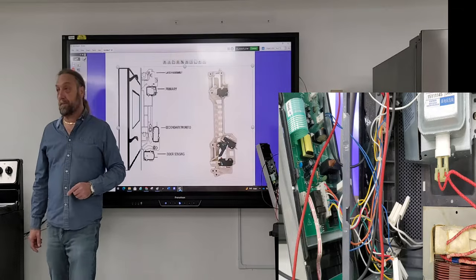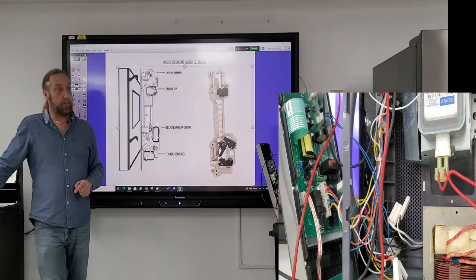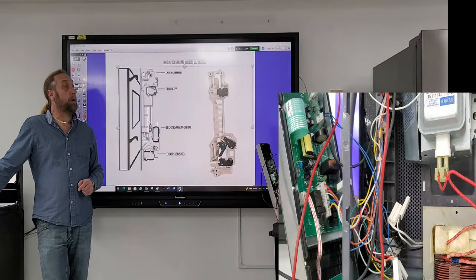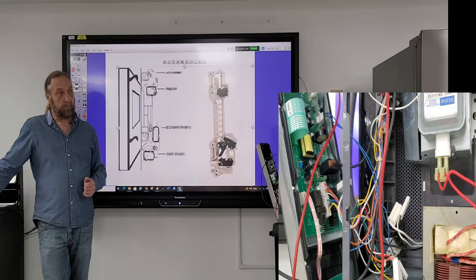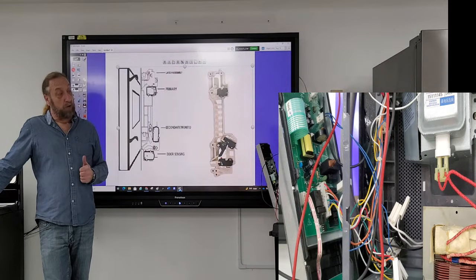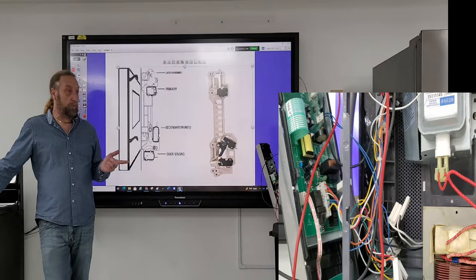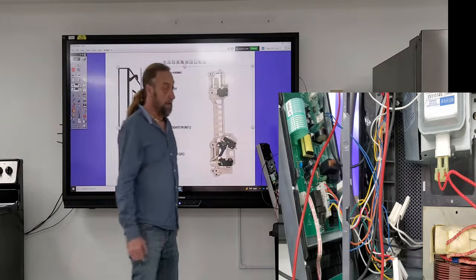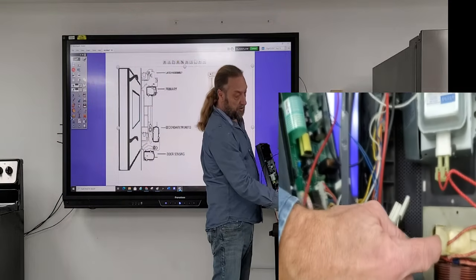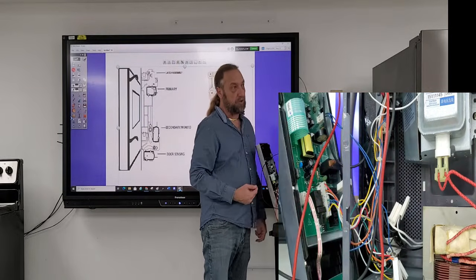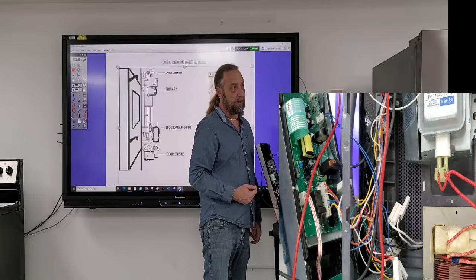Are you supposed to drain the capacitor before you check that? I'm sorry, what? Are you supposed to drain the capacitor before you check that? You should. Even though it's technically charged right now, you won't get no reading? Well, in order for that capacitor to shock me when I'm checking the door switch or the board, 2 things. One, that capacitor has to discharge through the transformer, and then the other side of the transformer has to discharge back into the machine before I get electrocuted.